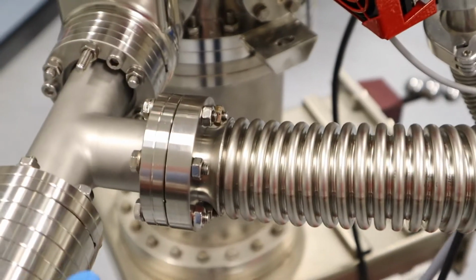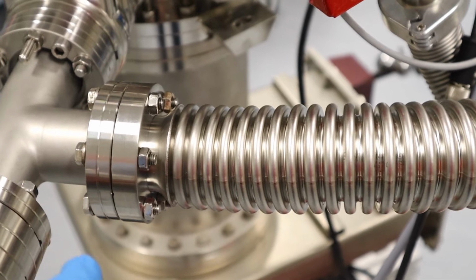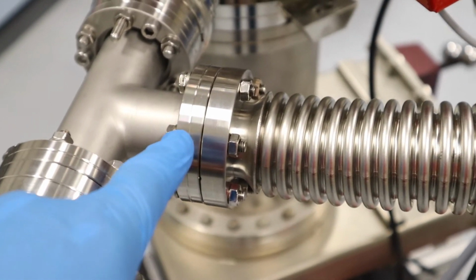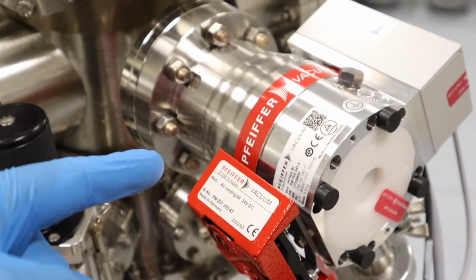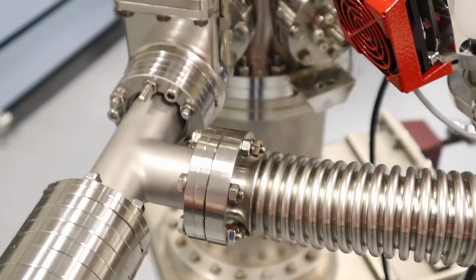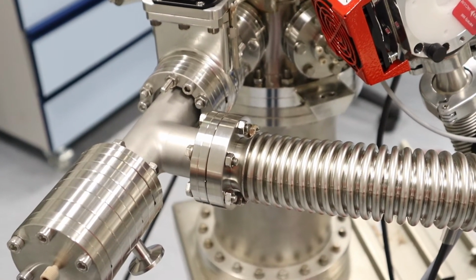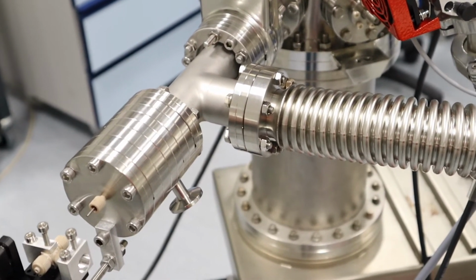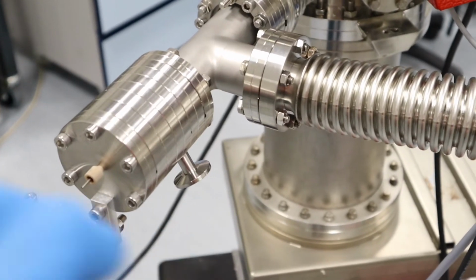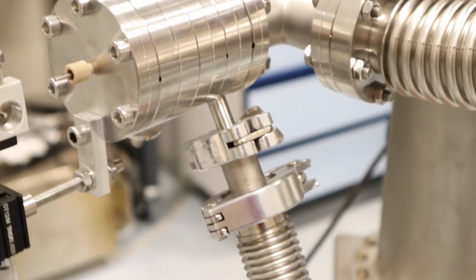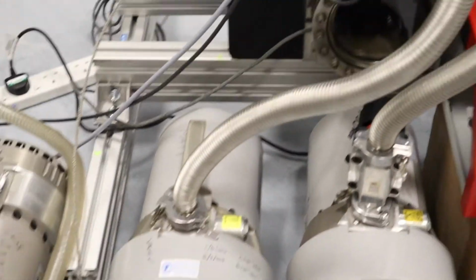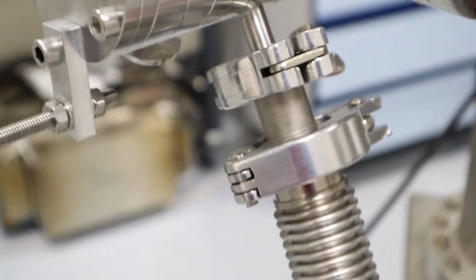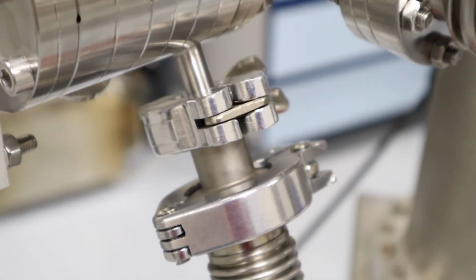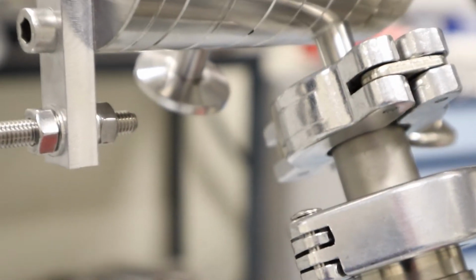Now the alternative is to attach the HiPace 80 or any small turbo pump directly to the pumping flange of stage 3. So we would possibly take a pump like this and attach it directly there. But like I said, for the purposes of this test, I'm just using the HiCube because that's what's readily at hand. Okay, so now we're going to attach the scroll pumps to stages 1 and 2. Now I've attached stage 2 to one of these SH110 scroll pumps, and I've used a reducing O-ring in here to go from KF16 to KF10. Now I'll do the same on the other port that you can just see in there.